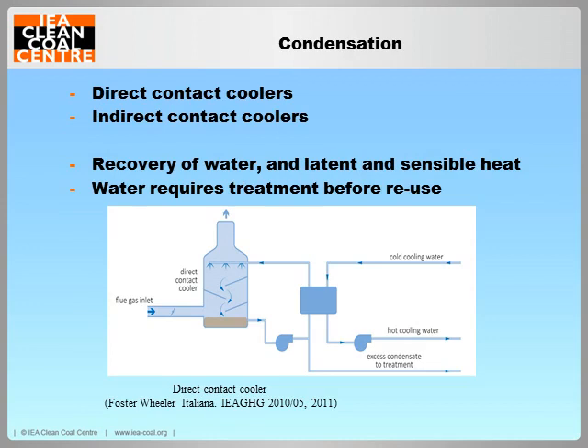Cooling the flue gas to below 50 degrees centigrade, which is the water dew point, would not only condense the water vapour, but also enable the recovery of latent and sensible heat. This recovered heat could be used to increase the net unit power output, and this would also lower carbon dioxide emissions.